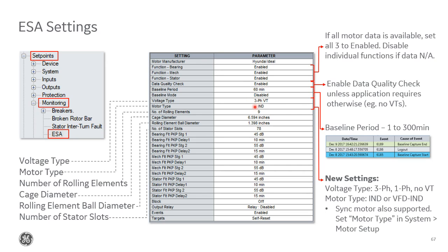Another couple setting options we added in firmware 2.7 are the voltage type and the motor type. The voltage type is what kind of VTs you have wired to the relay. So if you have three-phase VTs, a single-phase VT, or if you have no VT. We ran into a few customers who were applying this on motors that they did not have VTs for, which in the older algorithm, some of the calculations included voltage, so they couldn't use some things. Here we have the options. So if you choose something like no VT, then we adjust it accordingly. So we have this option added here.